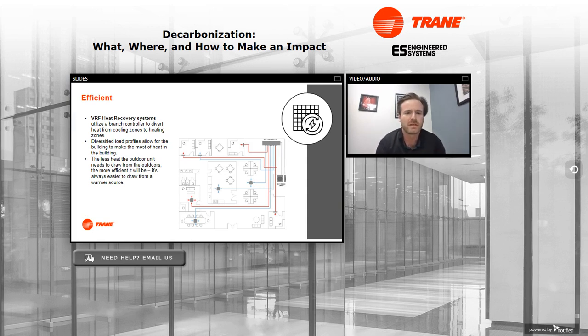Here we have a diagram showing how VRF efficiency can really help with an electrification project in a space. The red lines indicate heating zones where you're discharging heat into the spaces via refrigerant, and cooling zones are your blue lines. So if you have a conference room in the middle of the building where a big load can generate from a meeting, you can pull the heat out of that space and send it to your branch controller, and heat will be delivered to spaces that need it on the perimeter where you may have windows, for instance.